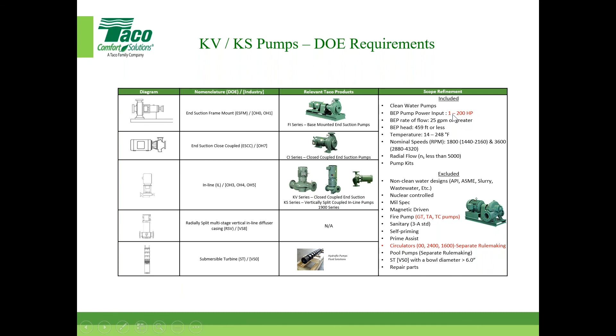DOE requirements: the Department of Energy, over 1.5 years old now, has put energy requirements on TACO products, specifically HVAC hydronic pumps. Two of the products I'm talking about today are affected, the KV and KS pumps. We've had to upgrade their design to meet basic requirements put forth by the Department of Energy. The range is 1 to 200 horsepower - anything above 200 horse we didn't have to address. The speeds covered are only 1800 and 3600 nominal speeds, so 1150 or 1200 nominal speed doesn't include that. Most of our KV and KS, to be honest, fall in that 1 to 200 horsepower range.